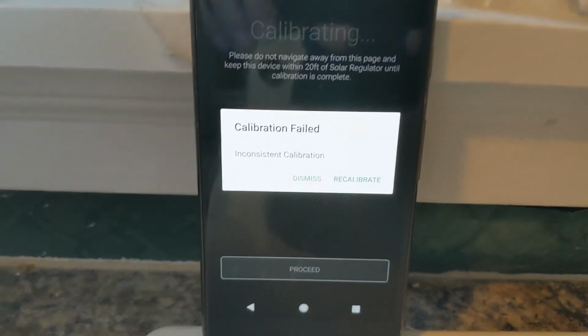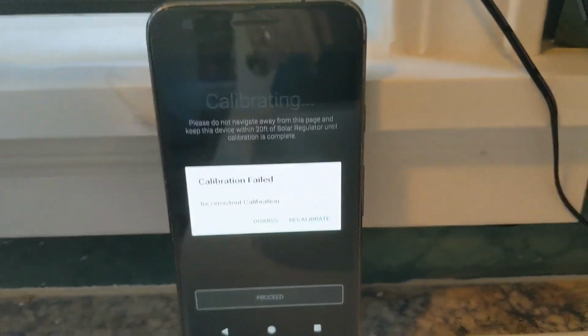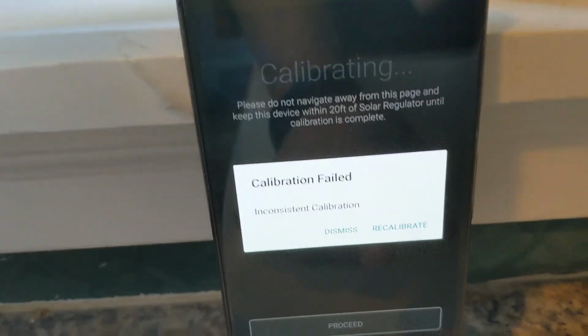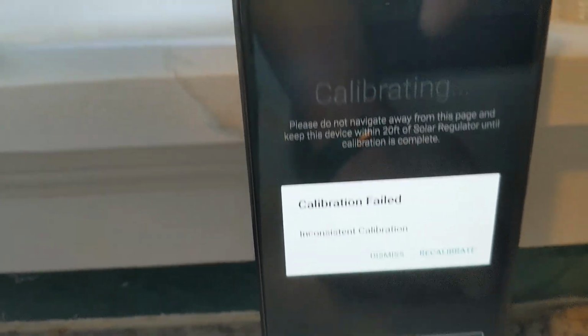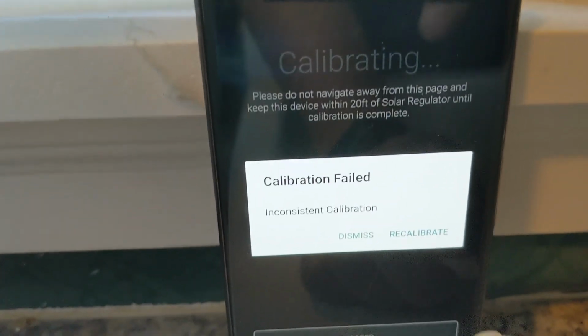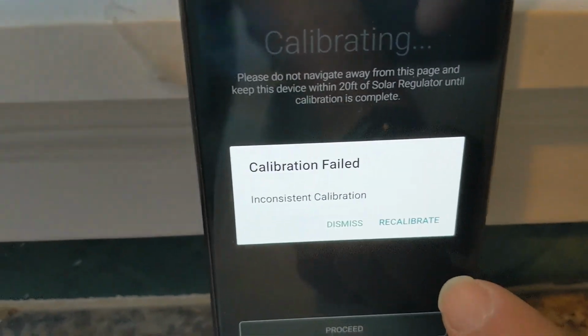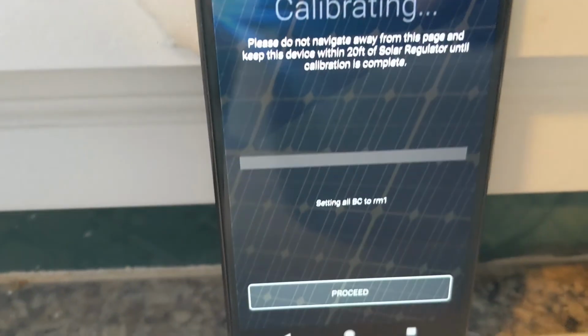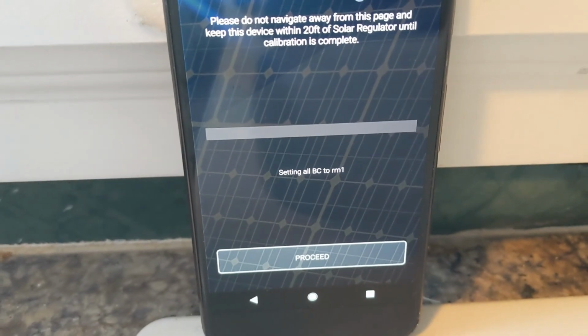Okay, this is a new message: inconsistent calibration. It's 1:17 and 31 seconds. It's possible this is my fault though, because I just ran the microwave, and one of the things they said not to do was drastically change the load. So it's possible that one's actually my fault.